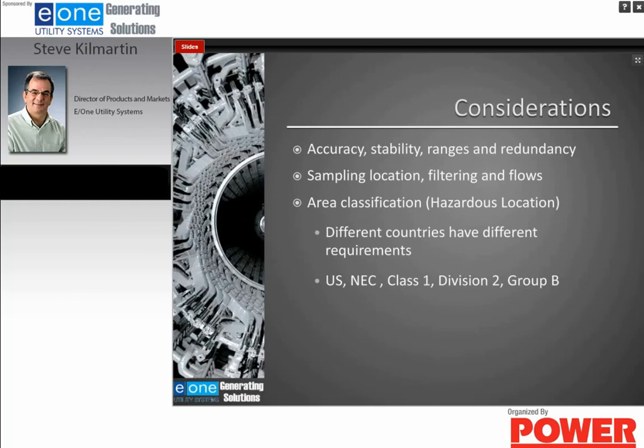Another very important consideration is area classification. Because you're bringing hydrogen into these analyzers or into these sensors, that area becomes a hazardous location. You need to have analyzers that are rated to be installed in a hazardous location. When you are purchasing an analyzer that has the controls and electronics that have to be in a safe area, you need to make sure that the sensor cell is the only thing that's mounted in the hazardous area.